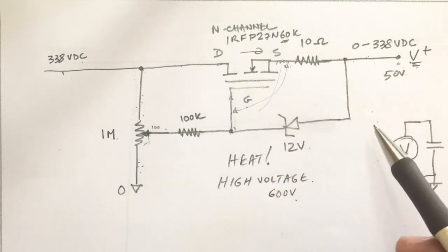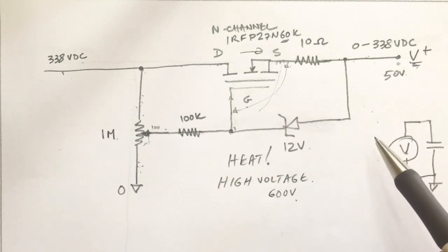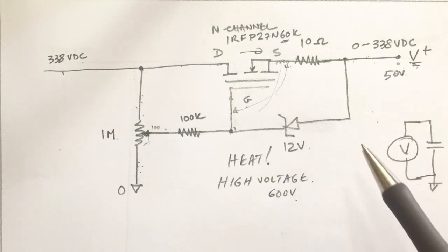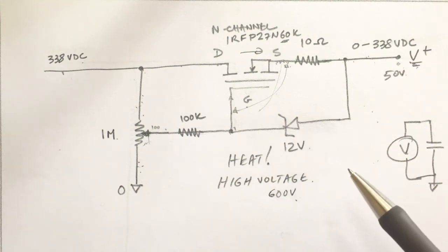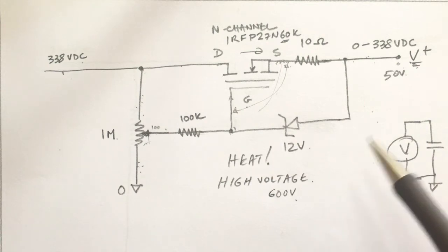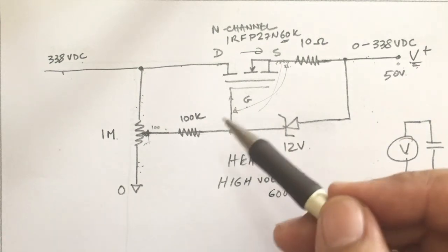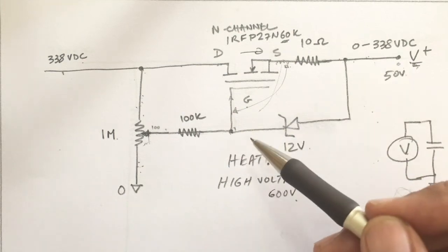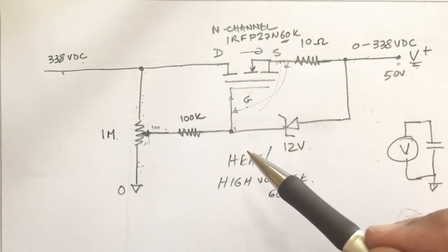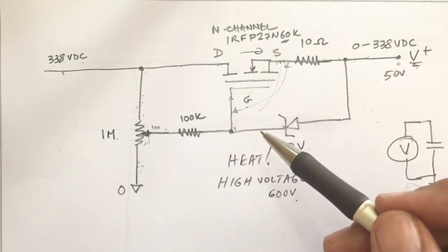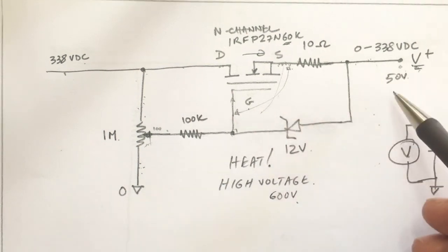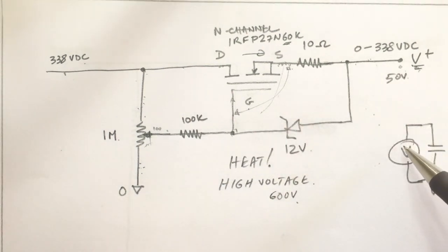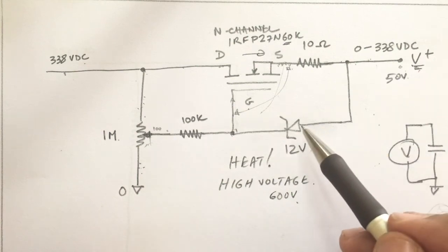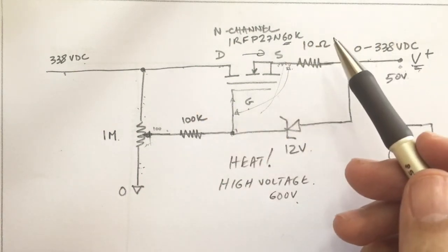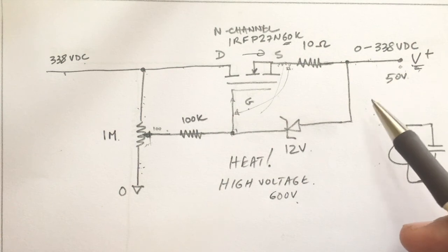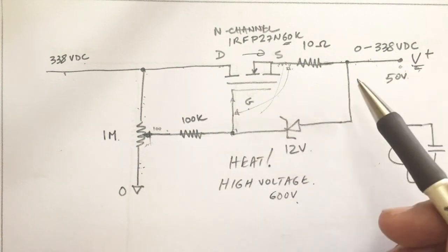The leakage current is actually fairly low—it should be very, very low, down to microamps if that. So you need a very sensitive ammeter. But if you put in a 100 microamp ammeter, which is common and easy to find, and you switch this on with very high leakage on a capacitor, your ammeter will peg and probably burn out, or if there's a short it'll peg and burn out.